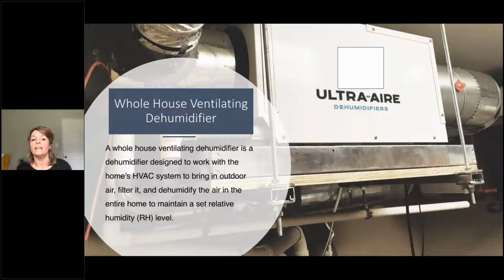So this is where we're seeing really the need for whole house ventilating dehumidifiers. So the dehumidifier integrates with the HVAC system, and it's only going to focus on the relative humidity. Set up that air conditioner to remove as much water as possible when it's running, but when it shuts off and the relative humidity is still too high, then the dehumidifier will come on and dehumidify the entire home. So in the evening time, a lot of times you go to bed, someone gets up, starts cranking down the air conditioning because they're uncomfortable. It usually isn't a temperature thing, it's a relative humidity thing. And our shoulder seasons, that's when we're really going to see the dehumidifier shine and do the work.